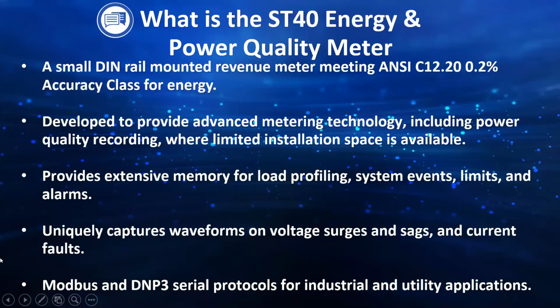So now going into a little bit more detail on the ST40 meter. This is a small sized DIN rail mounted revenue meter, and it's got very high accuracy. It's certified to the ANSI C12.20 0.2% class accuracy for energy, so it's really accurate. It's developed with very advanced metering technology, just like all of our other meters in the Shark and Nexus metering line. It's obviously giving you your power quality recording. This meter also has extensive memory for load profiling. So not just looking at what your energy consumption is right now, you can actually go back and see how much your machinery or apparatus is consuming in terms of energy over the last week, last month. You can compare it month to month. You can compare May of last year to May of this year.